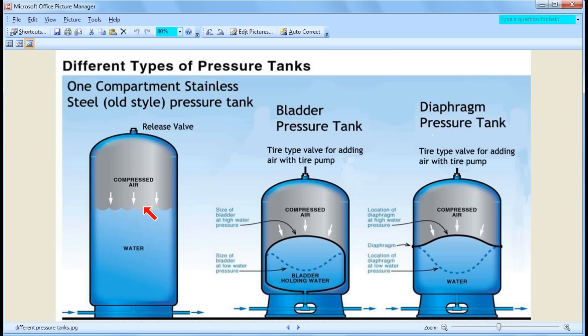You might ask whether the bigger stainless tank costs more. The answer is not really — even though the tank is much bigger, the stainless tank is much cheaper than the bladder or diaphragm tank. So the most cost-efficient choice isn't immediately obvious: it's bigger, cheaper, but doesn't have a lot of drawdown. To answer that we need to do a little analysis, which I'll do later in this video.